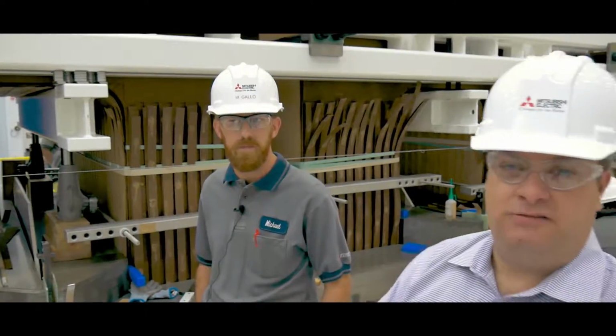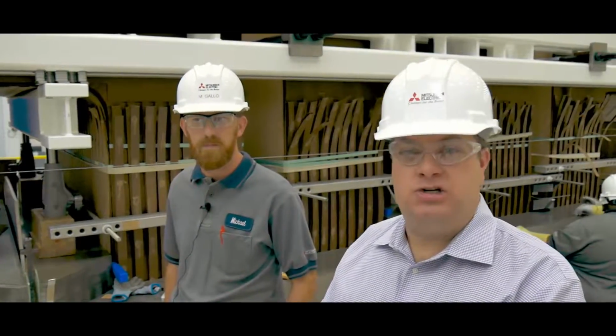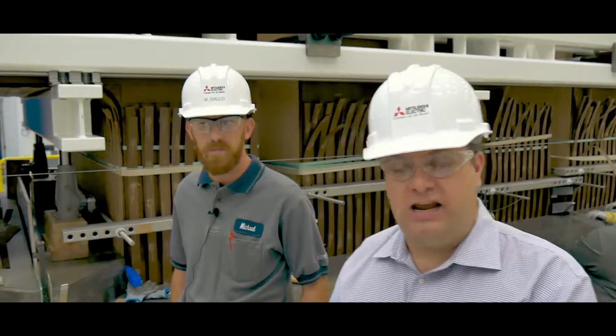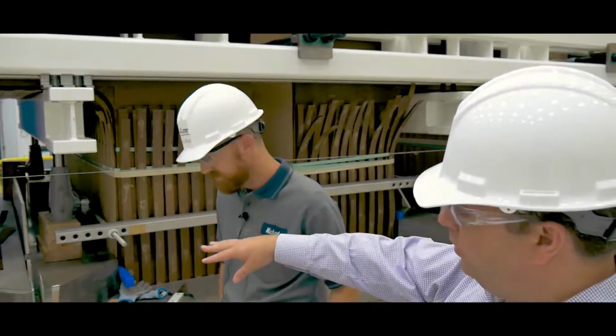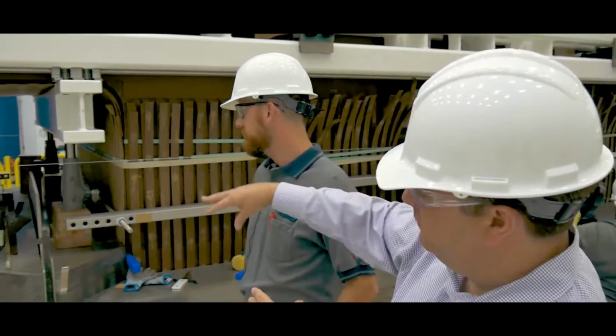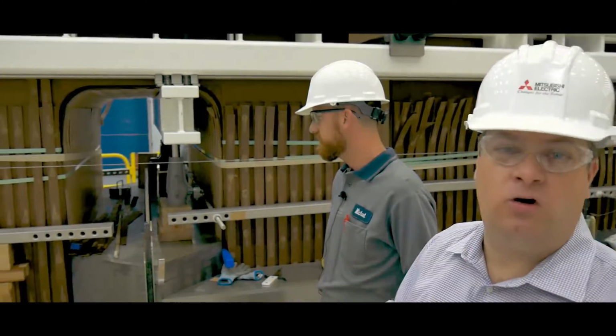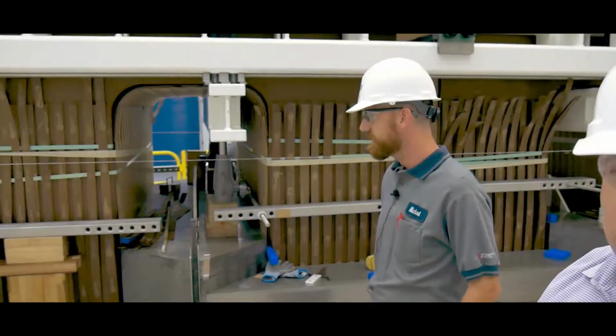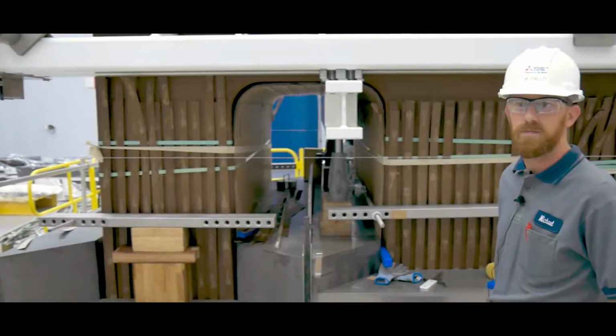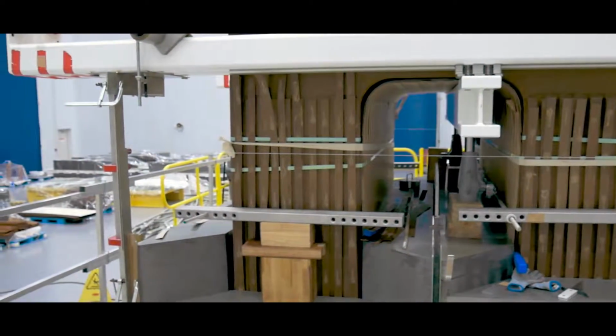Our particular design of transformer is called a shell form transformer. It gets its name because the core passes through the center of the winding, but also around the perimeter, or sides, of the winding. So we say the core forms a protective shell around the winding.